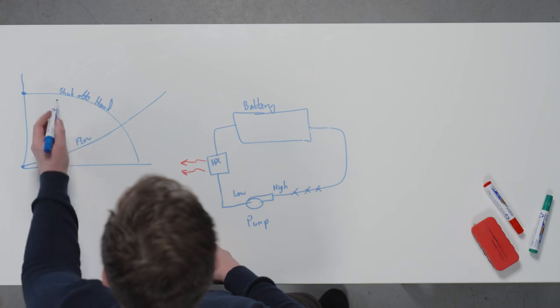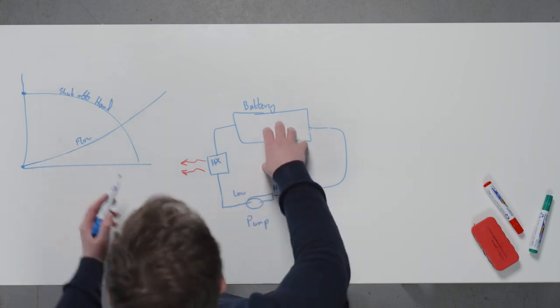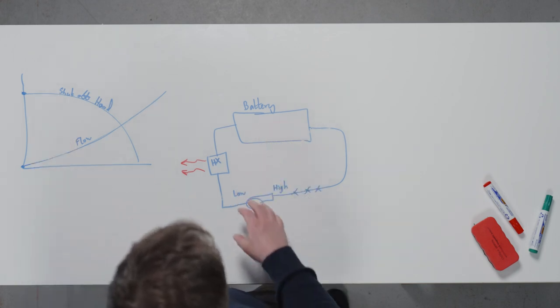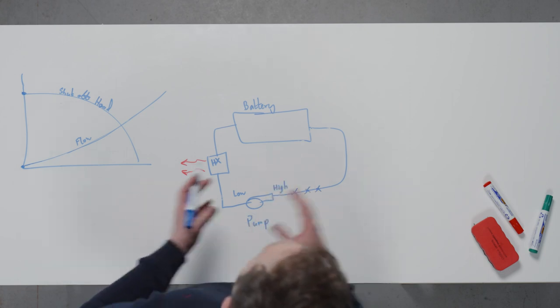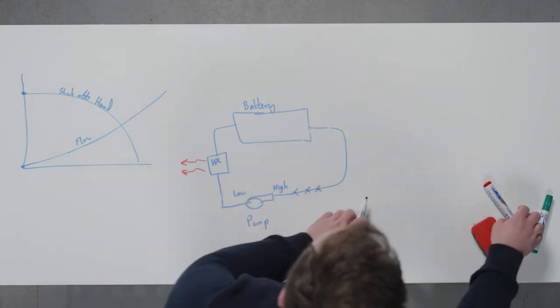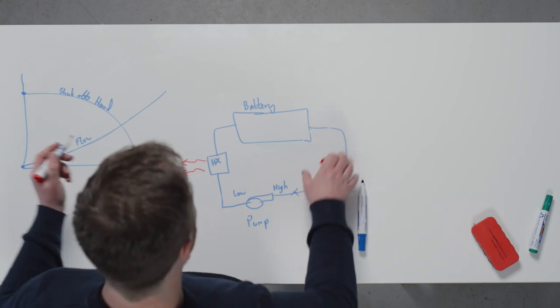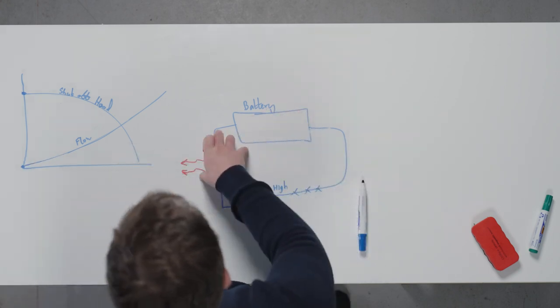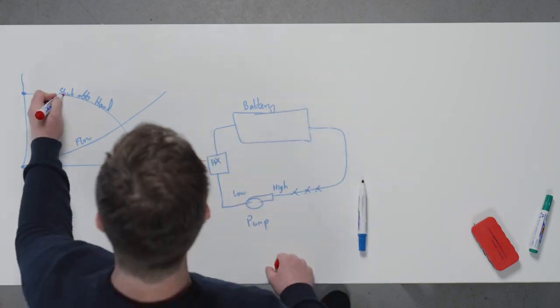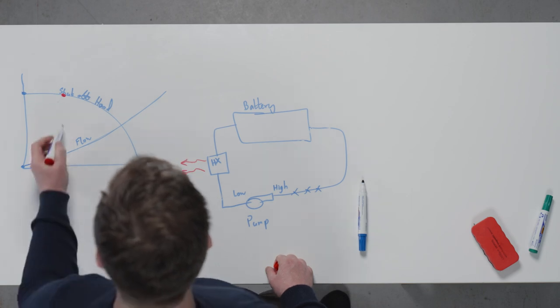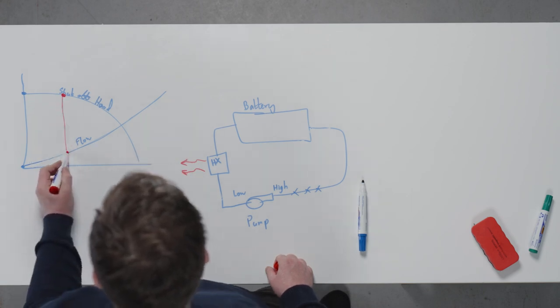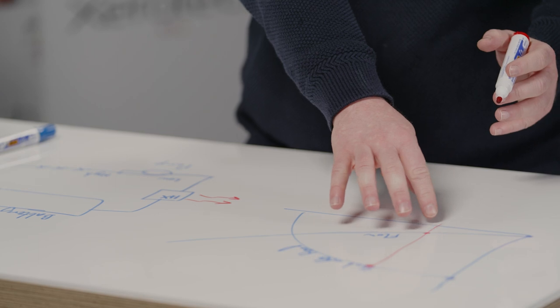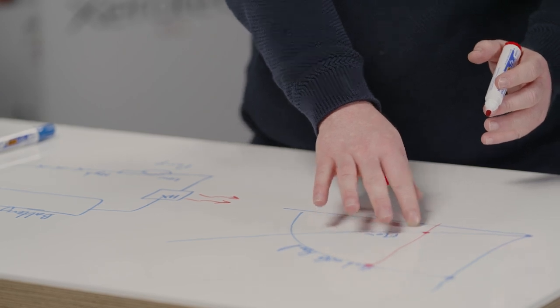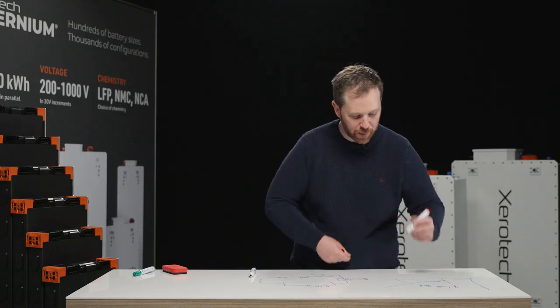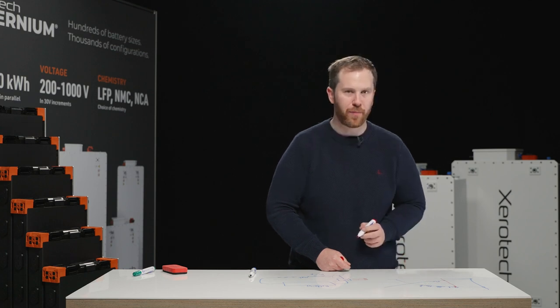So when we look at our pump curve here, in all real systems, there's going to be some amount of pressure drop or head pressure that you have to overcome to develop a flow through a system. And what that means is, once we add real components into this system, it's going to push us somewhere down this curve. So when we come back, you're going to develop only a certain amount of flow rate for that given system. And our goal is to develop as high a flow rate as possible.